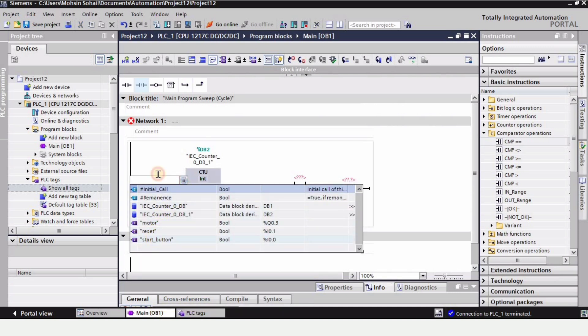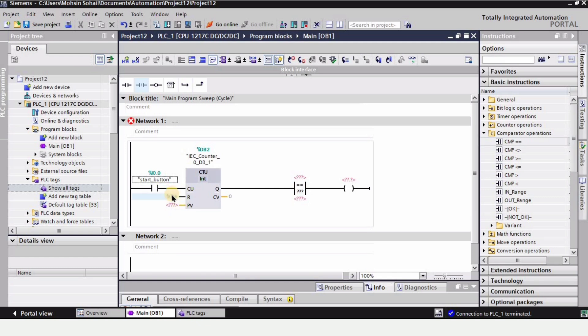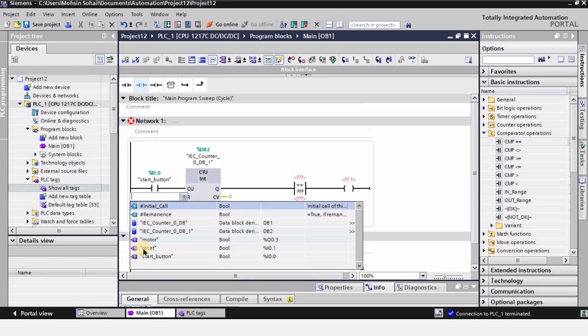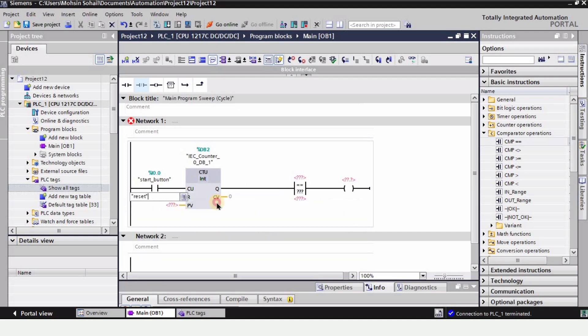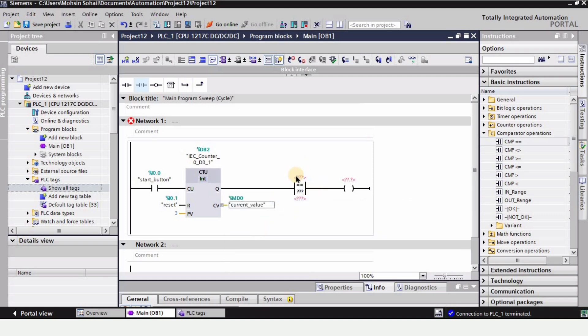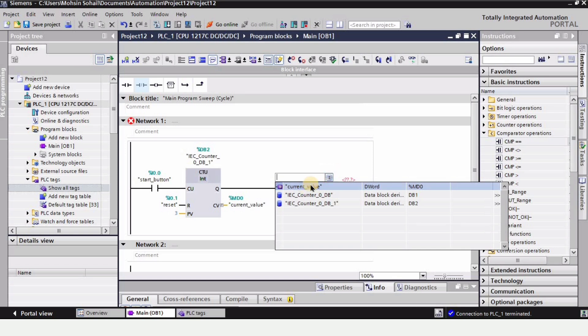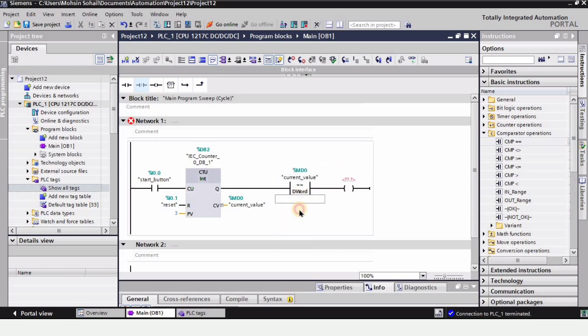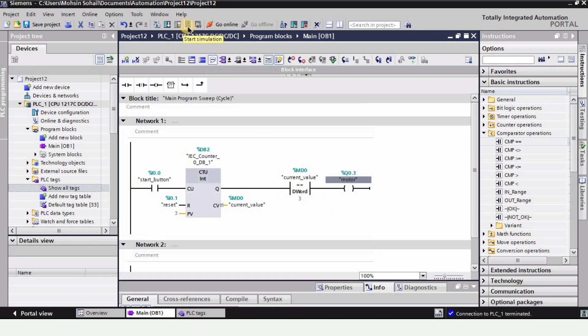Now let's assign all of the tags. This is the start button, this is the reset button for the counter. For the CV I will use the current value tag we just created, assigned to address MD0. This will be the same current value, and I'm going to set the comparator value to 3. So this will be comparing the current value of the counter and checking if it is equal to 3, and this is going to be the output.